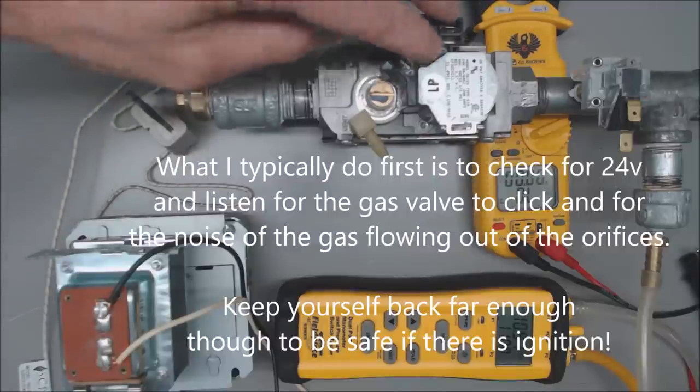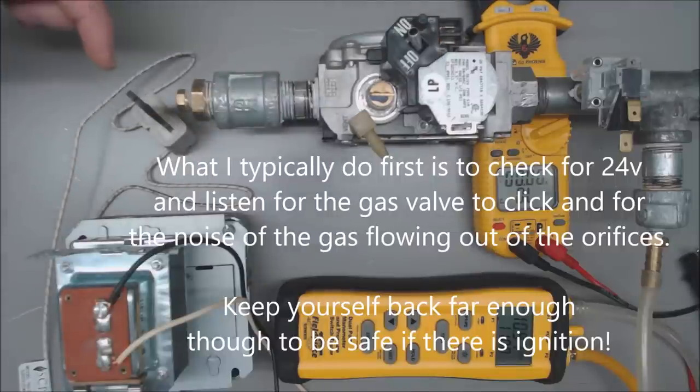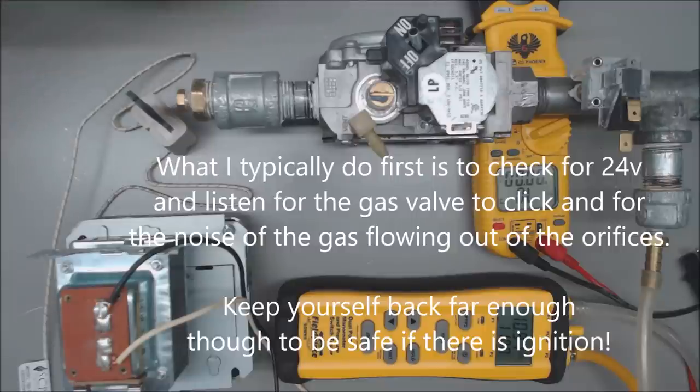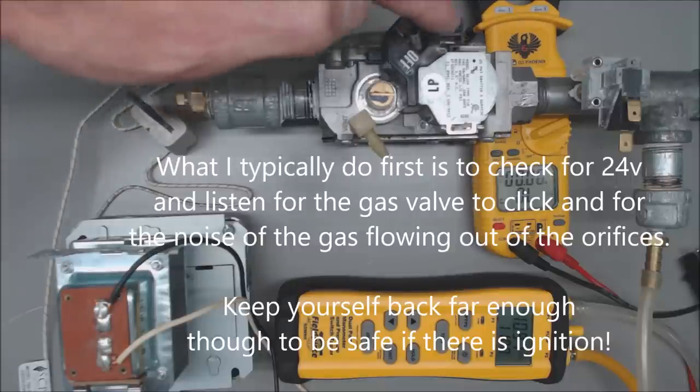The 24 volts is only going to occur for likely about three seconds while this hot surface igniter is cherry red. So that's the time when you need to check for your 24 volts there.